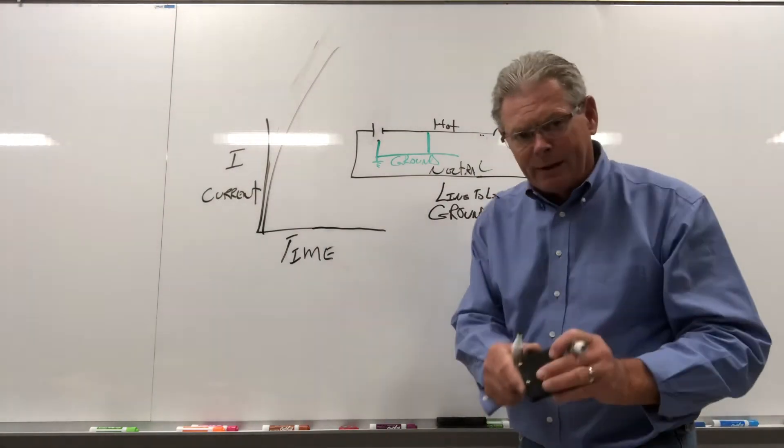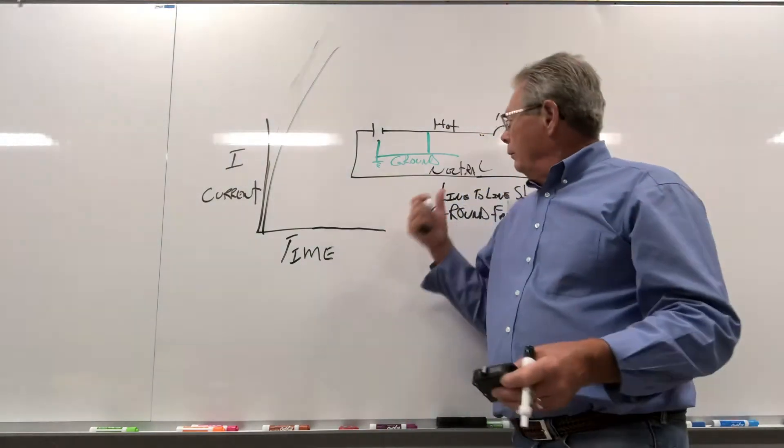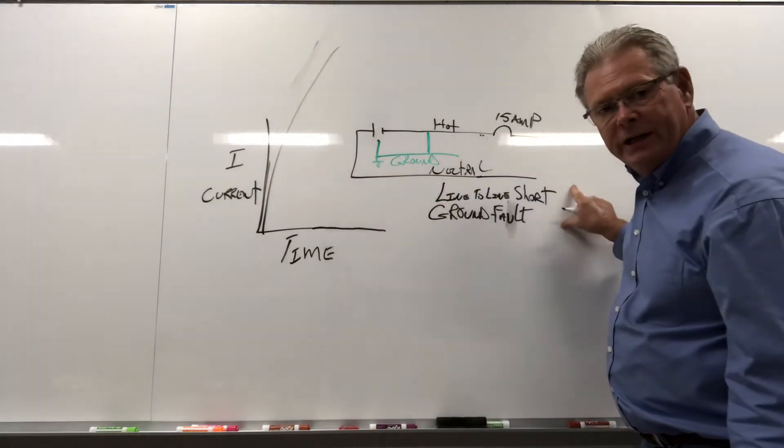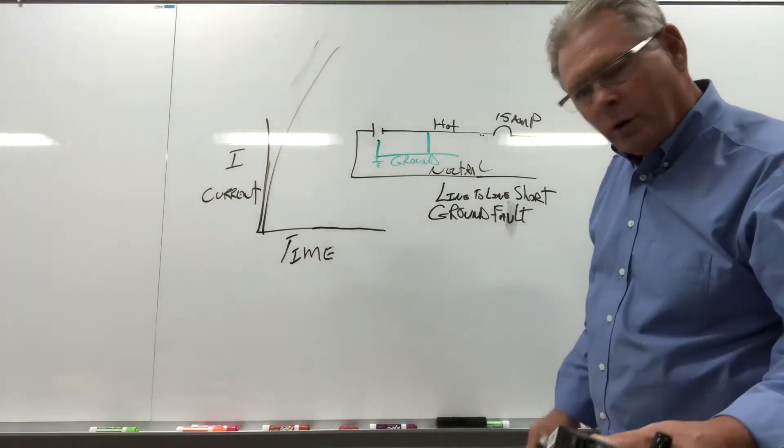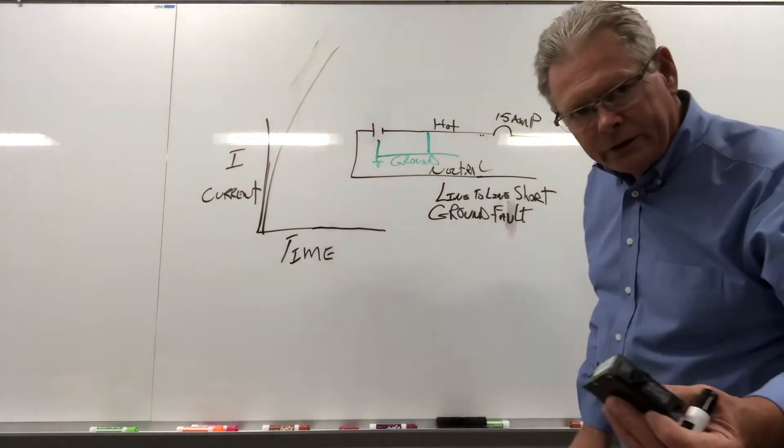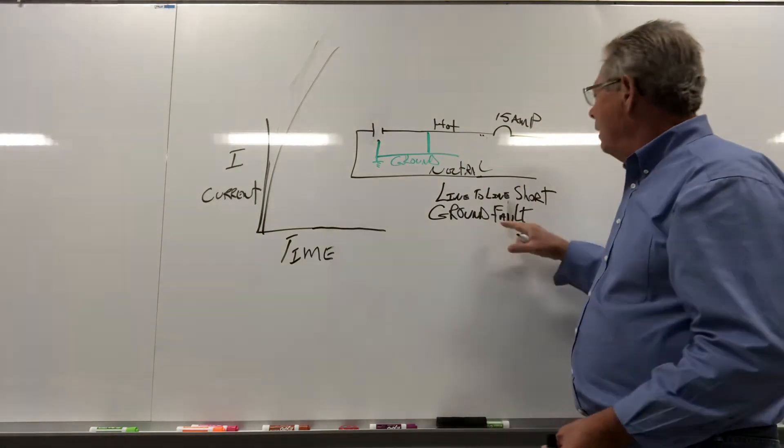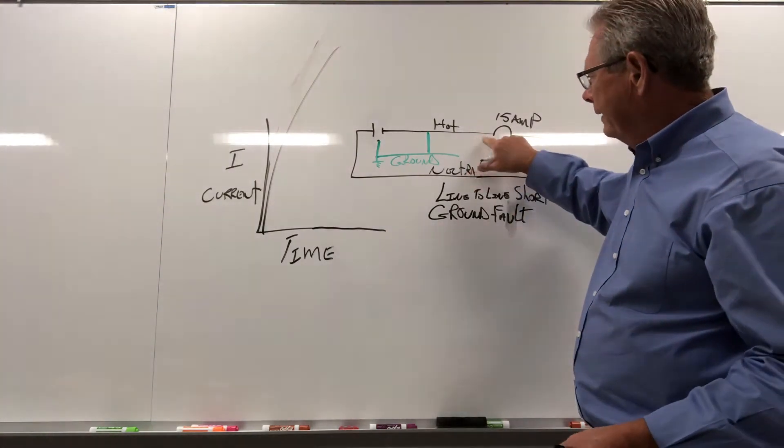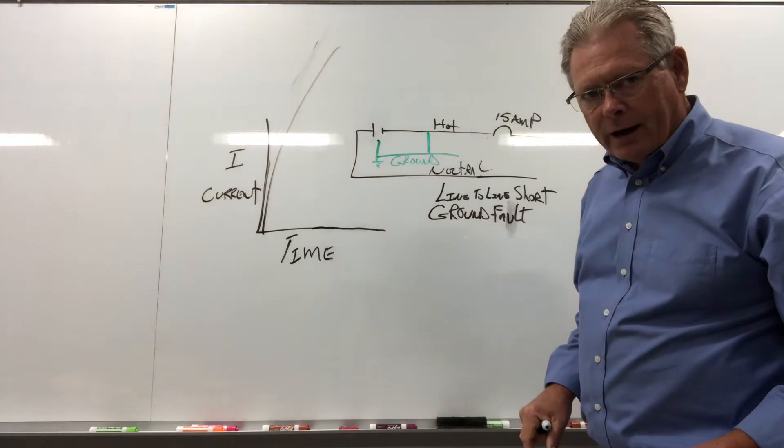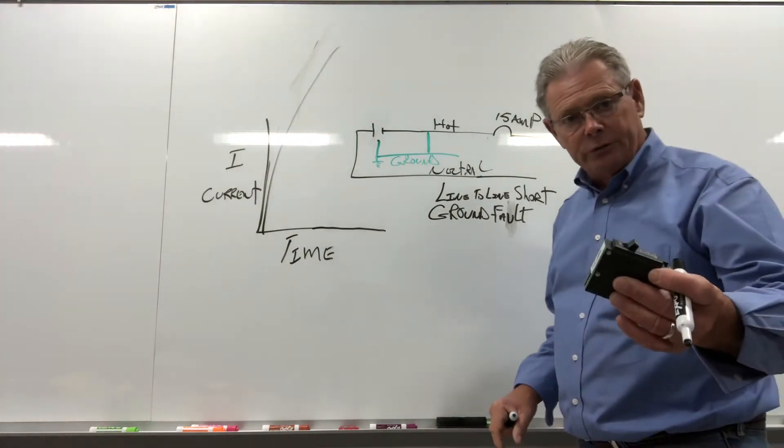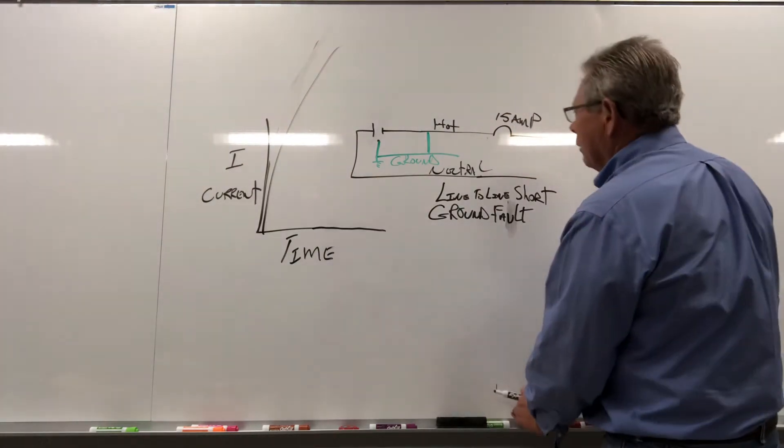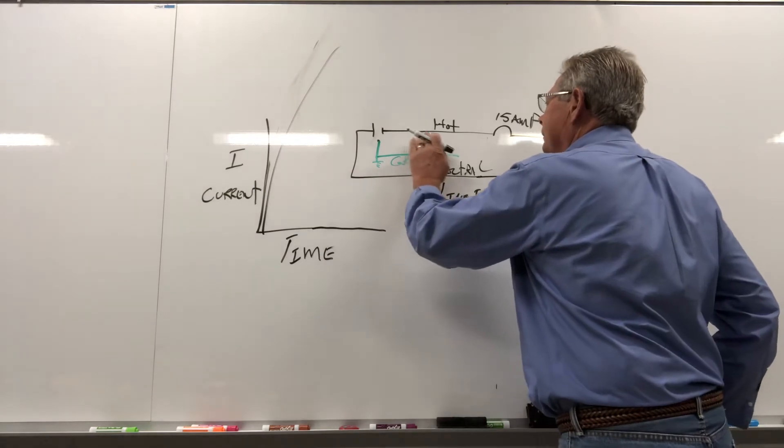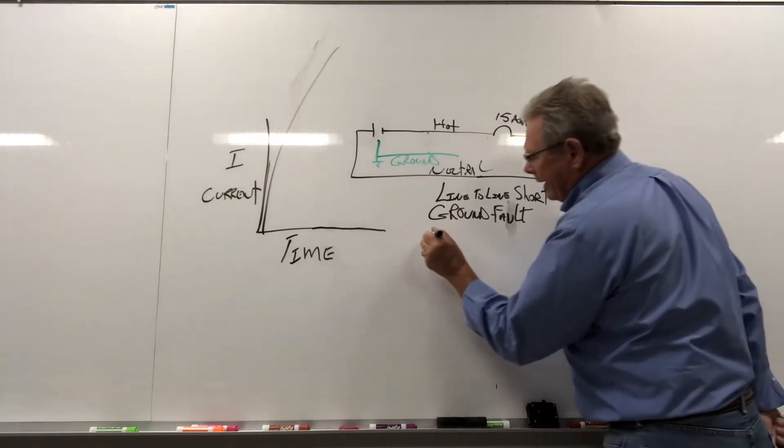So if you reset a breaker and it goes pow, probably looking for one of these two conditions, a line-to-line short for 120 volts to be line-to-neutral, your current-carrying conductors. Or it can be a ground fault where your hot has come into contact with your ground. Does that help troubleshooting? It should. Okay, let's remove that short, and let's talk about an overload.